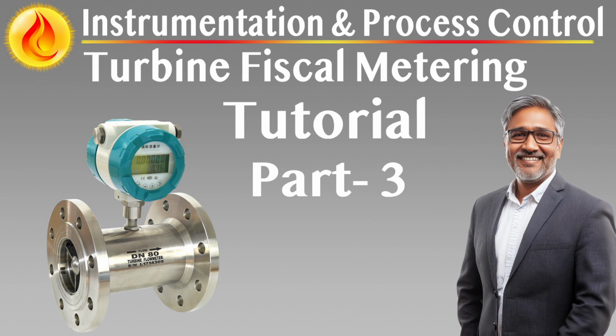Flow straighteners, flow profile stabilization for metering accuracy. Flow straighteners are mandatory in each metering run to eliminate swirl, turbulence, and asymmetric velocity profiles that would otherwise affect turbine meter accuracy and repeatability. The straighteners must be installed directly upstream of the turbine meter in accordance with the required meter tube lengths to condition the flow before it enters the rotor chamber.